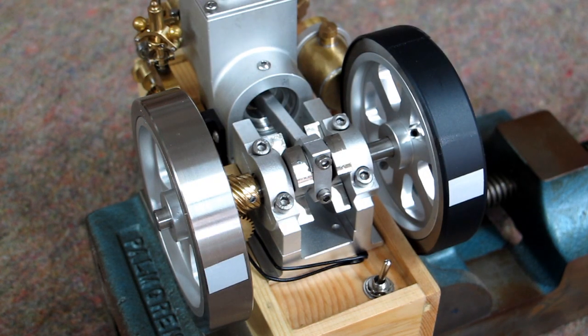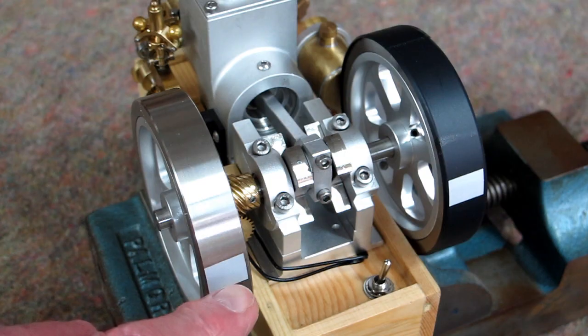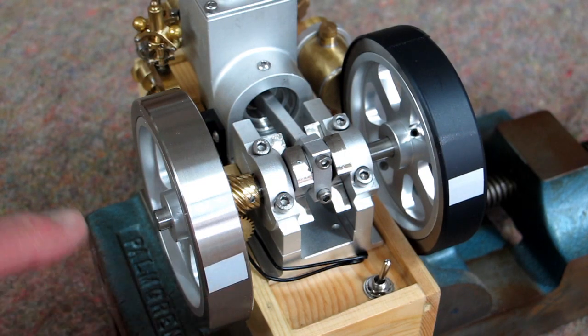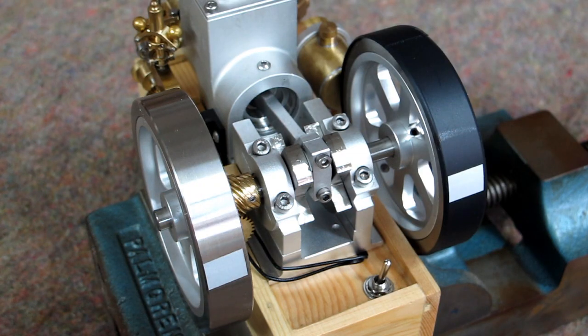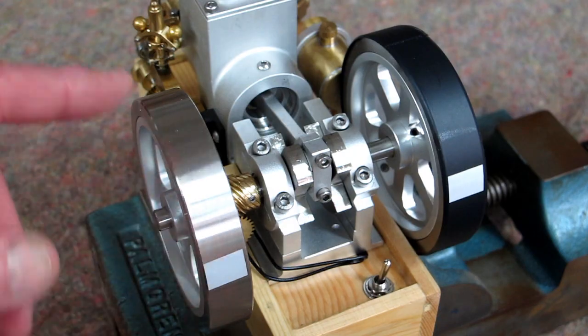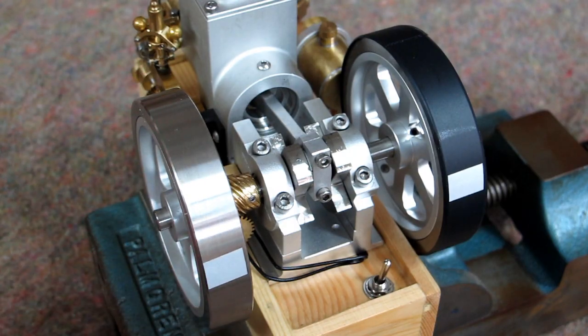Another thing you can do if you have a relatively low RPM, you can put a piece of tape here and one directly opposite. You'll get two reflections for each revolution. You divide the reading by two or you could put three on here and put them at 120 degrees roughly.